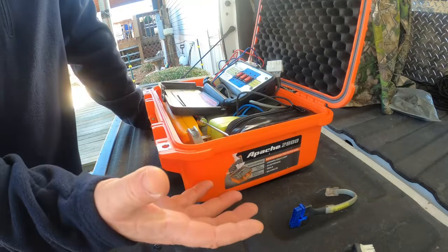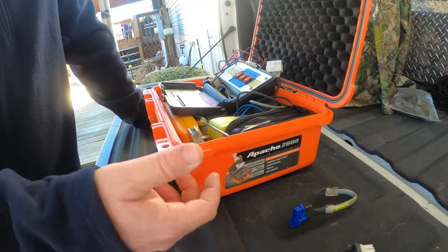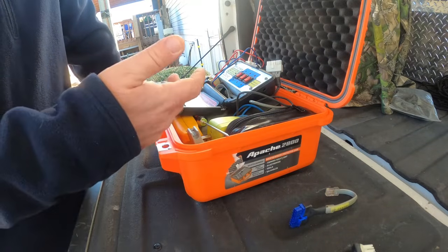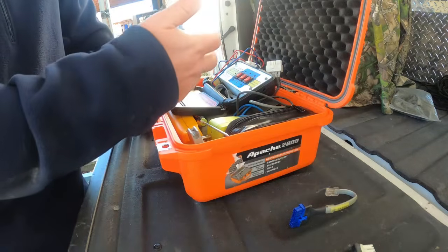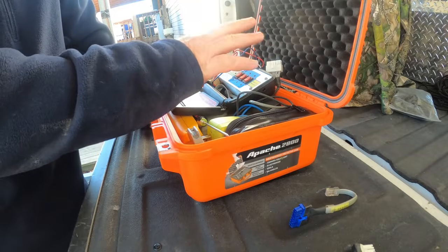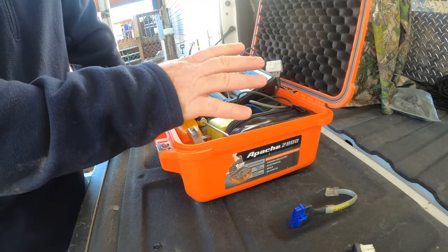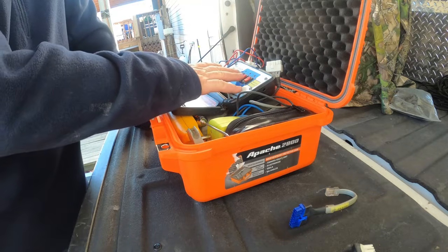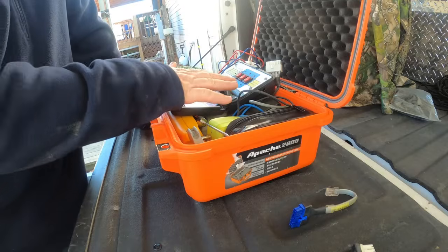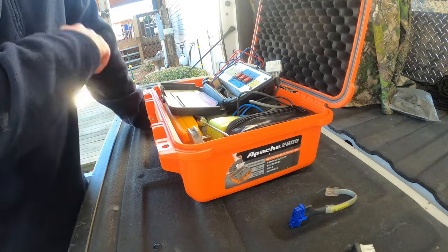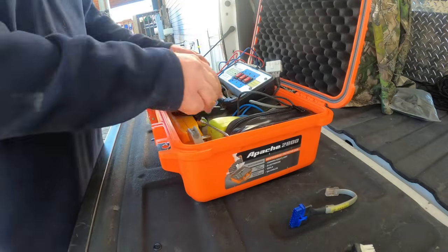And as far as the variable speed motors and X13 motors, you can ohm those out: remove your module, ohm out your windings. Typically all your windings, when you go between everything, it's going to ohm out at 0.8, 0.9 on all selections, regardless of whether you're doing low to high to medium coming back around. You're going to have the same ohms. So once you've determined your motor is good, if your motor is not hot and you don't have open windings and everything's ohming correctly in the motor and that wheel's spinning free, the motor's probably okay. You can just go with a module, not a problem.